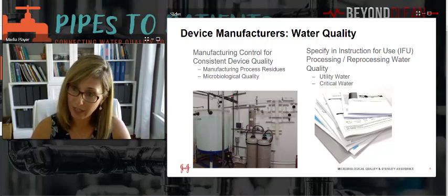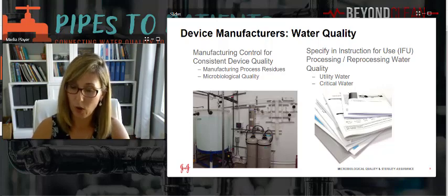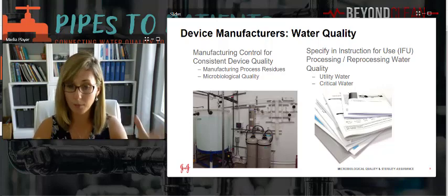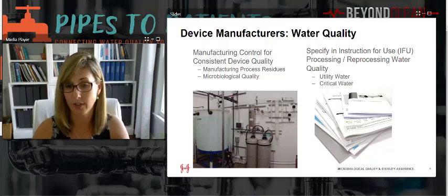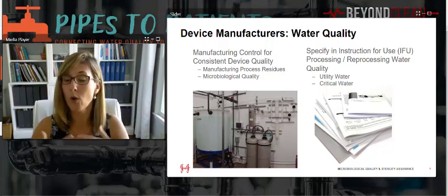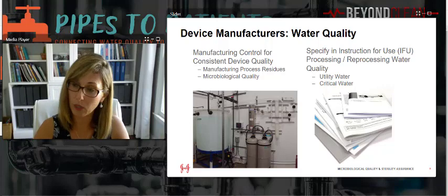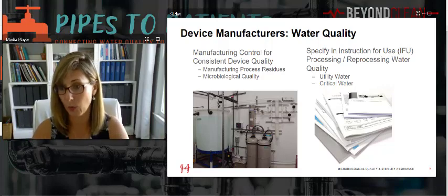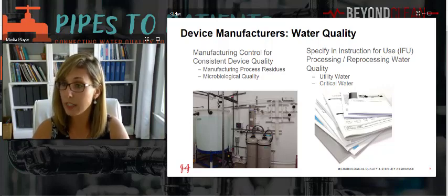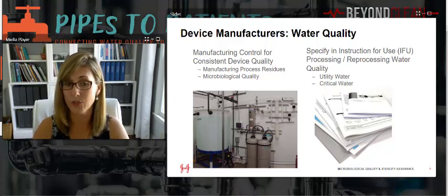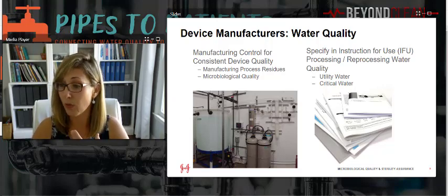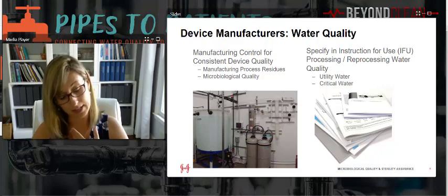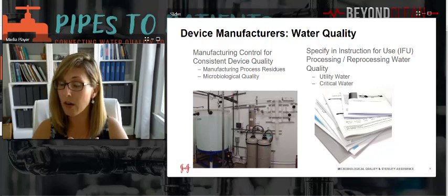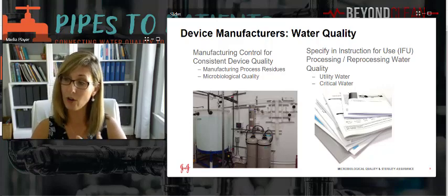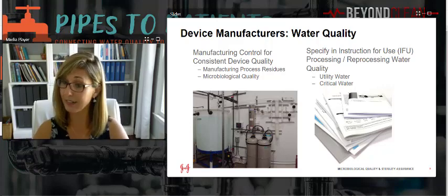So how do we communicate that level of water quality to you? So I think Alpa probably told you about manufacturer's IFU, which you are all very familiar with, where we actually specify for different parts of the process what water quality is required. So you might see terms like utility water or critical water as two of the recognized terms from the AAMI standards, AAMI guidance documents TIR 34, that indicate what that water quality level should be and how to make sure that your system is maintaining that.